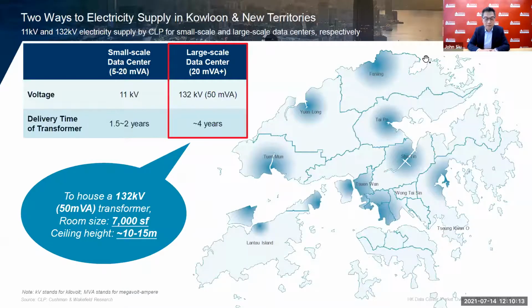For power companies in Hong Kong to provide power to data centers, there are 2 sources. One is the 11 kV power network - for power companies to provide that, from the date of application to the date of delivery takes about 1.5 to 2 years. If a power requirement is more than 20 MVA, then a 132 kV transformer has to be built at the site, and the time required for that is 4 years. In fact, this is one of the bottlenecks for converting or building a data center in Hong Kong.